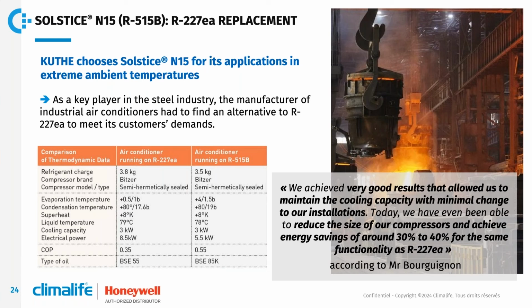And in this table, we compare all the conditions of the old system based on R227ea and the new one. All the conditions are very, very similar, especially the evaporating temperature, the condensing temperature, the superheat, the liquid temperature, and the cooling capacity, meaning the same needs for both cases. But the difference here is in terms of energy consumption. As you can see, for the first case, we consume 8.5 kilowatts, and for the second solution based on the use of R515B, low GWP, the energy consumption is only 5.5 kilowatts. That means we have here 30 to 40% energy saving, which is a very, very interesting solution.